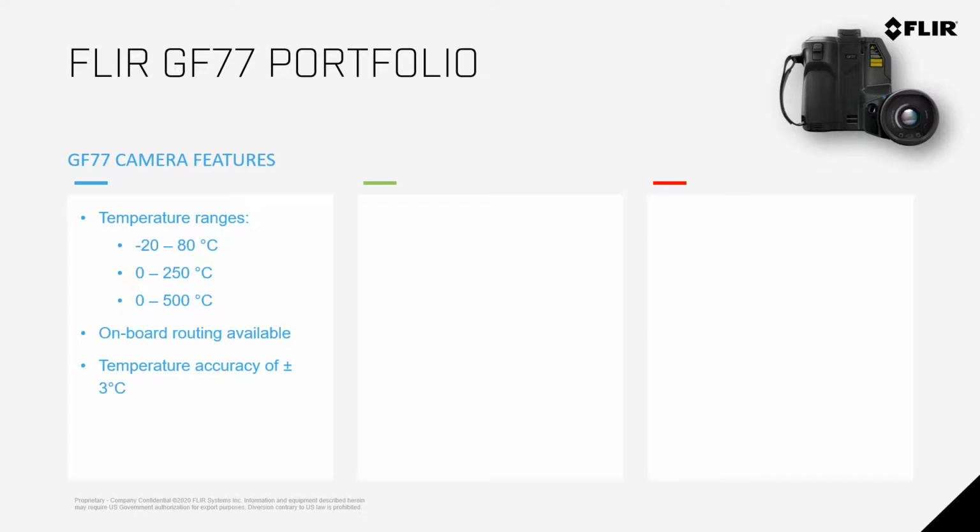The temperature accuracy of this camera is plus or minus 3 degrees Celsius, which is really good. Definitely when you're doing your thermal inspections, if you have something that's 150 degrees, but you know it shouldn't be more than 100 degrees, you know you've got an issue. Using thermal imaging cameras is about heat anomalies.